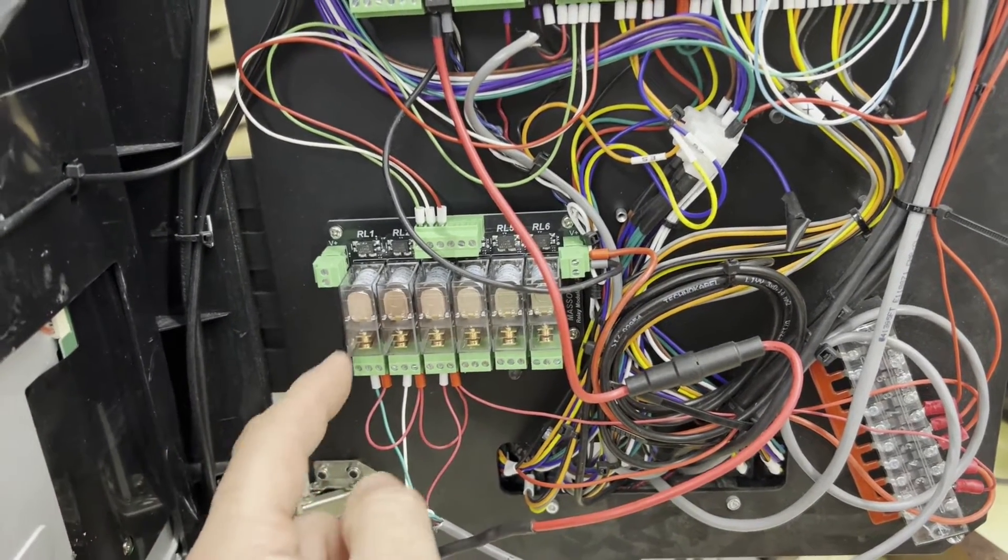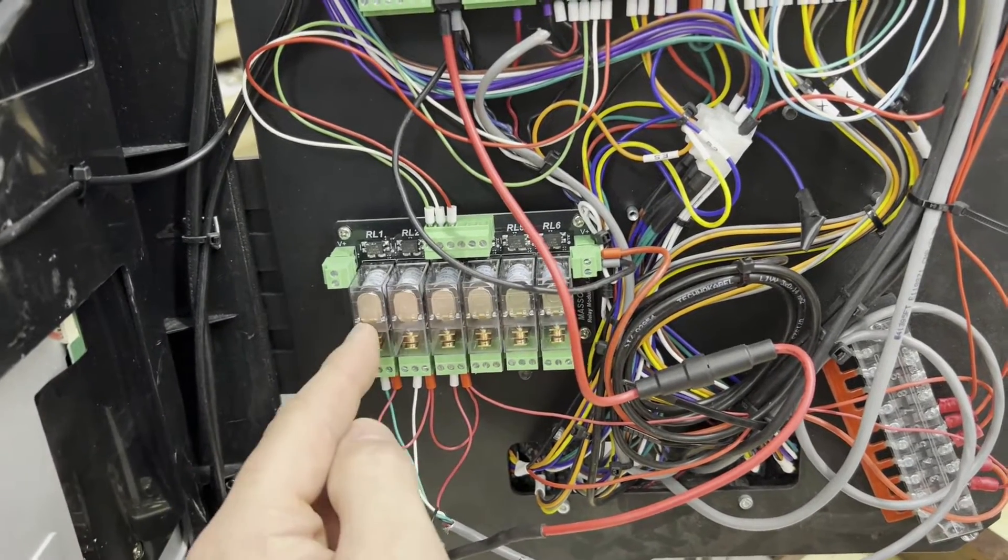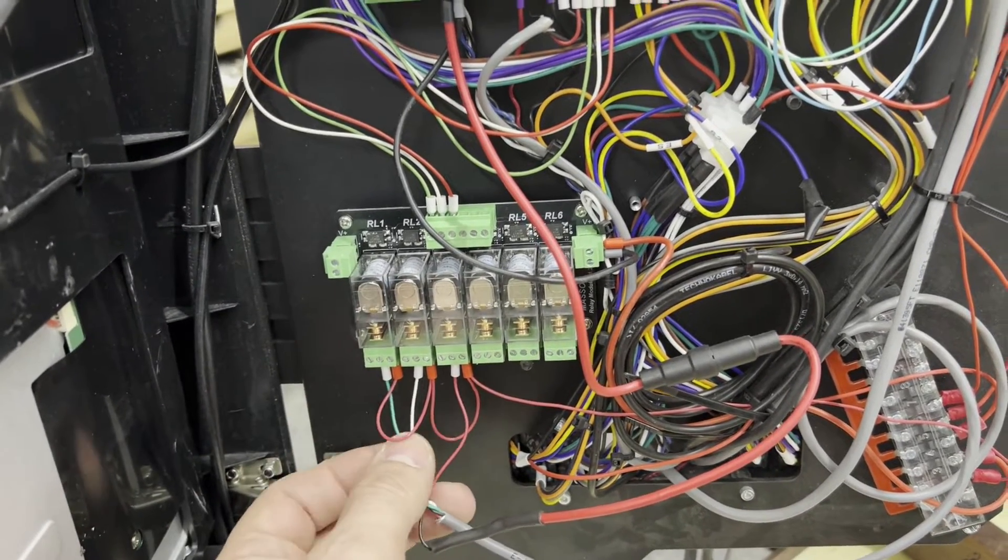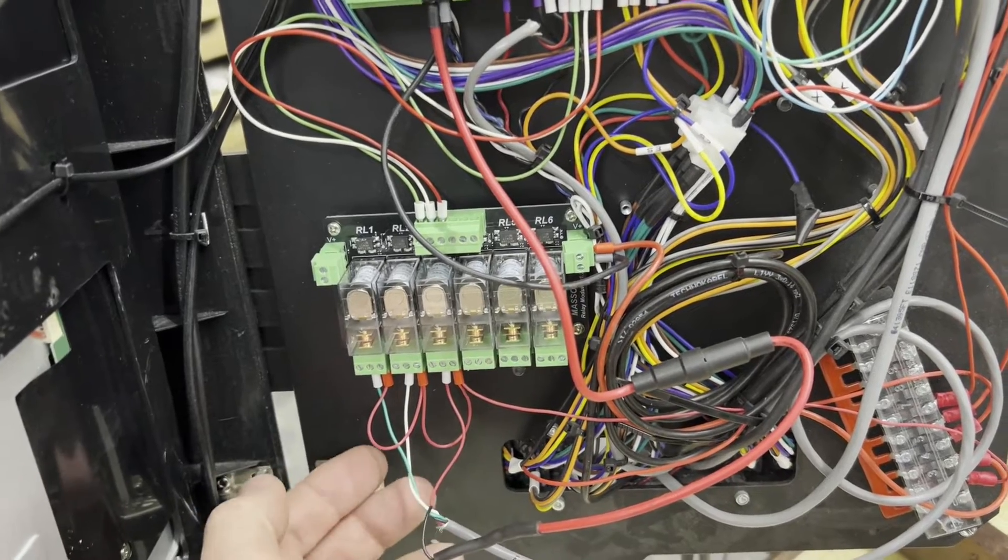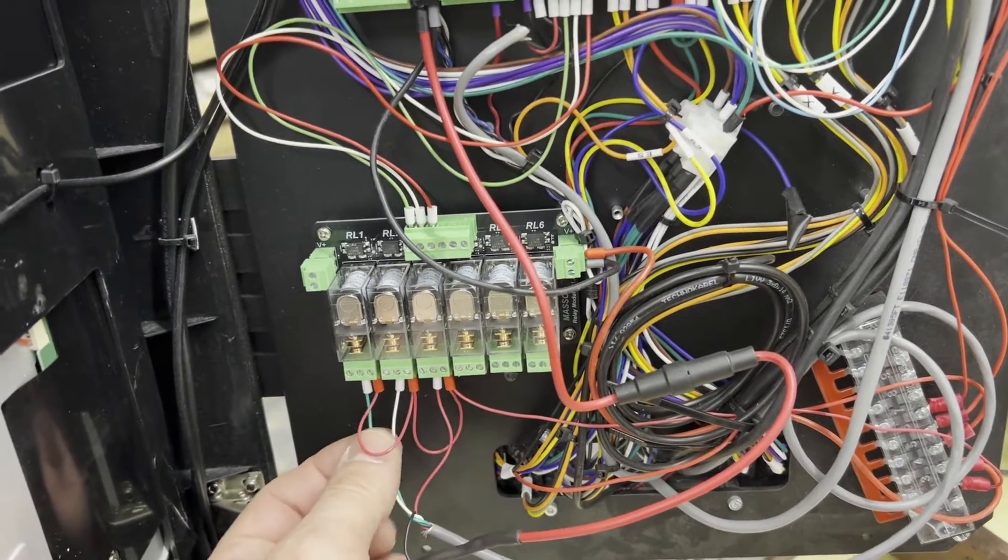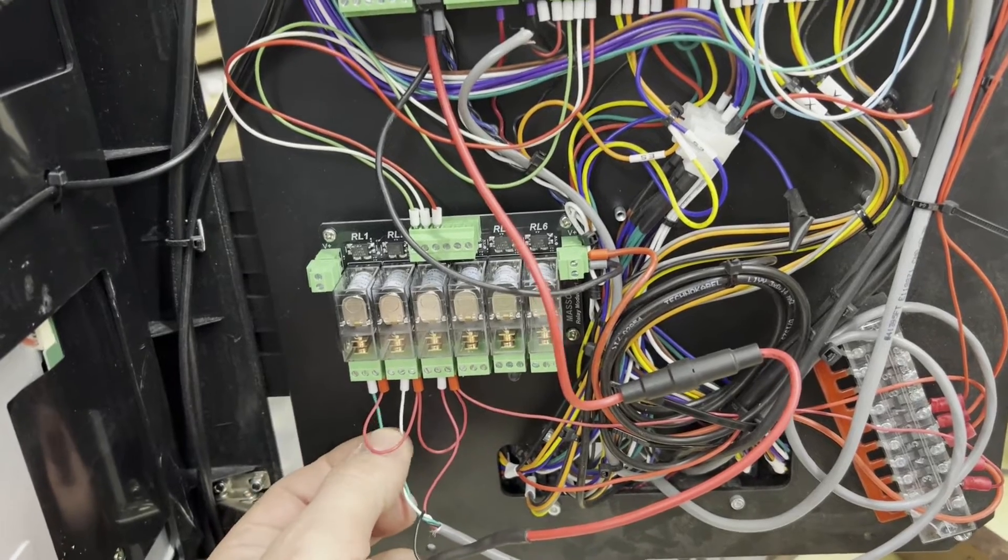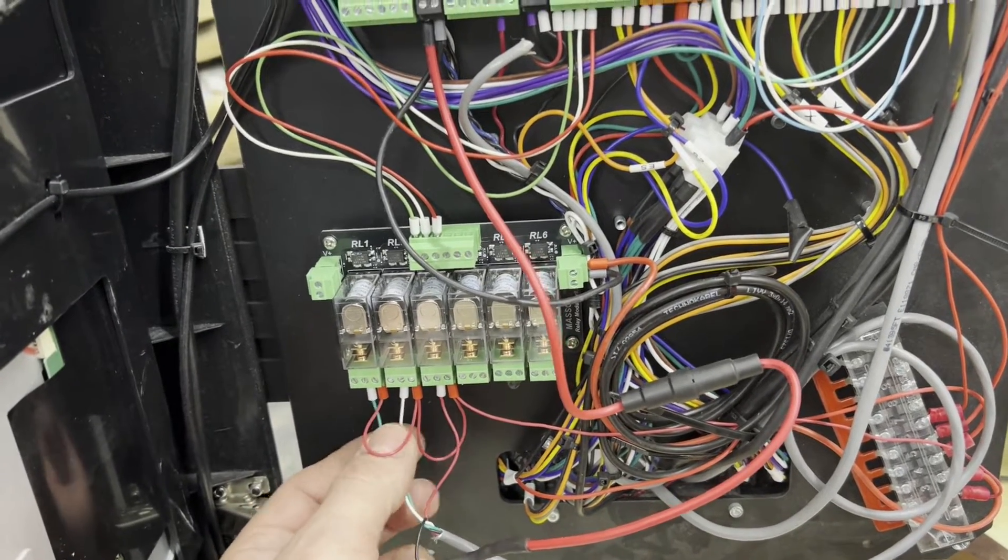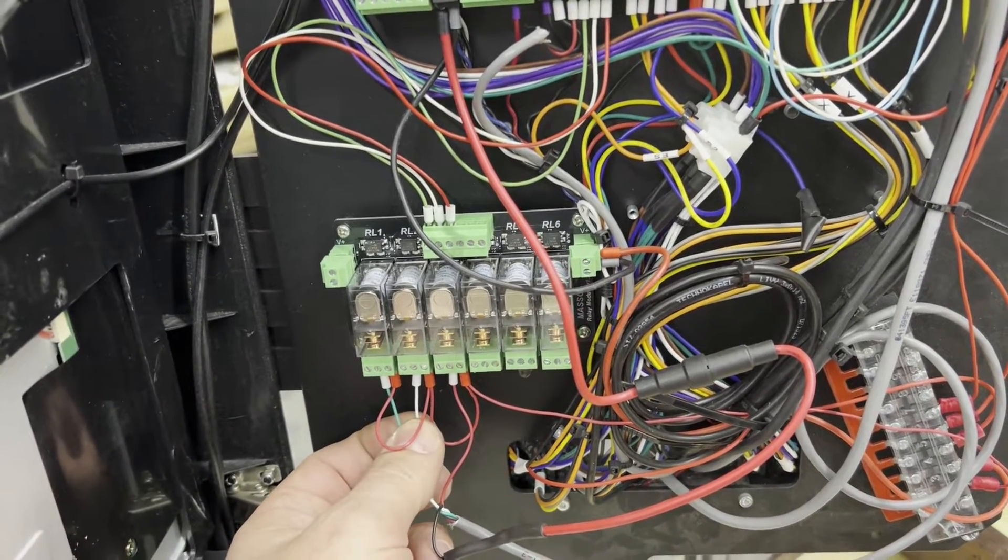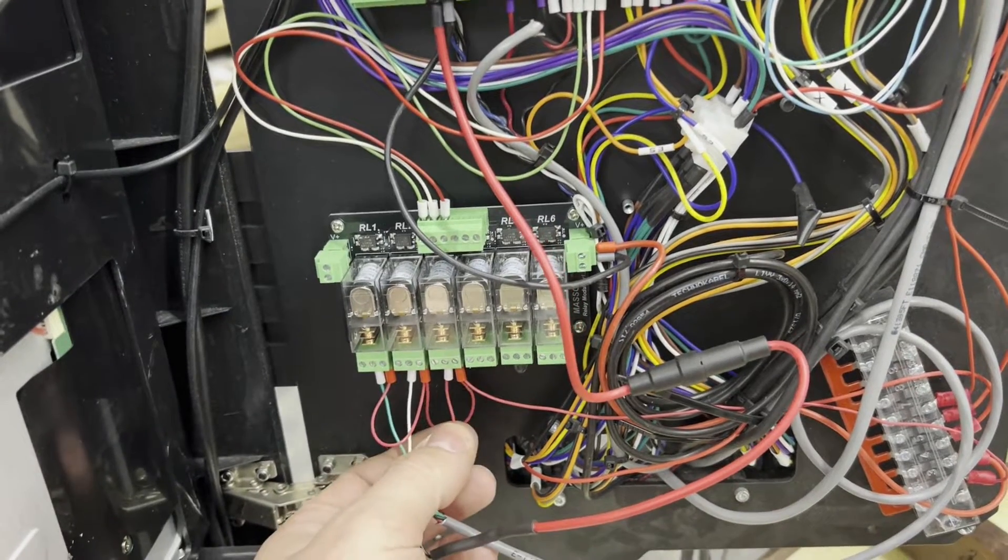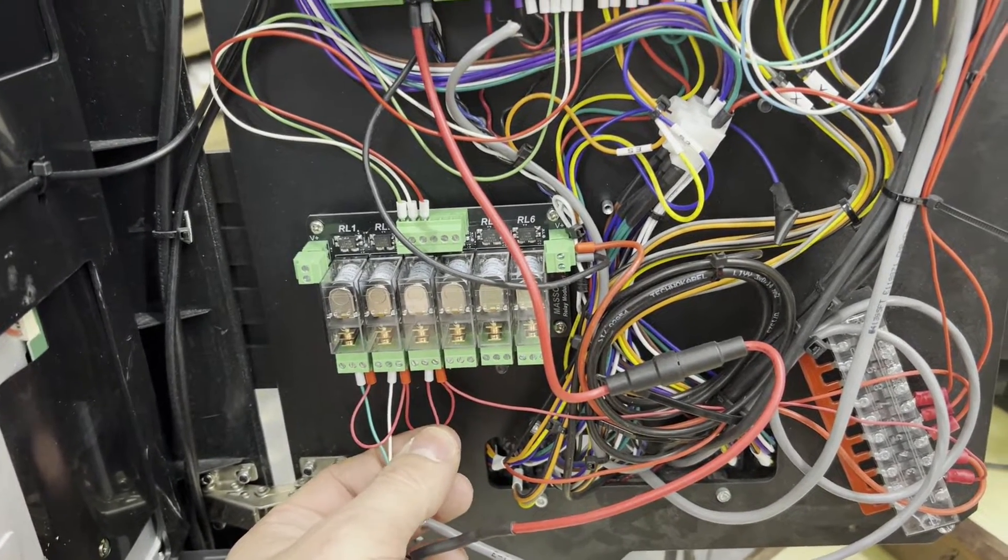Okay, on the normal open in the center of each of these terminals, on these relays, we're going to wire kind of color coding them according to our alarm. So, the first one will be green in the center. Boy, I got to get my colors right. The next one will be yellow or white in the center. And the last one will be red in the center for the red alarms.